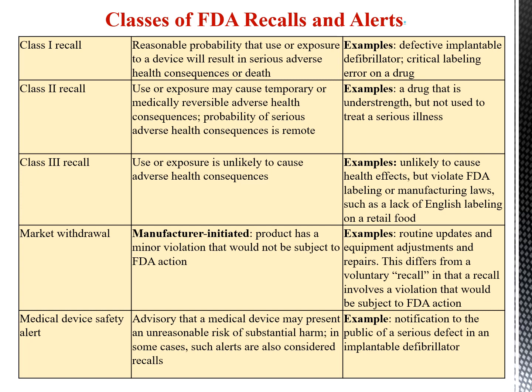The next is market withdrawal. Manufacturer initiated. The product has a minor violation that would not be subjected to FDA action. The manufacturer himself initiates the withdrawal. Example is routine updates and equipment adjustments and repairs. This differs from a voluntary recall in that a recall involves a violation that would be subjected to FDA action. Market withdrawal does not require an FDA action, but a voluntary recall may involve a violation that would be subjected to FDA action.